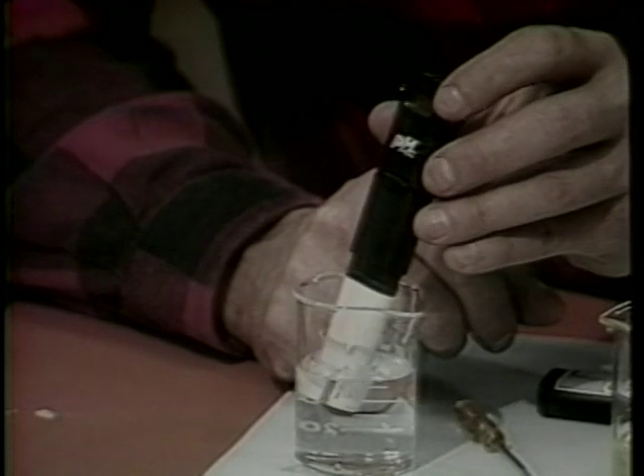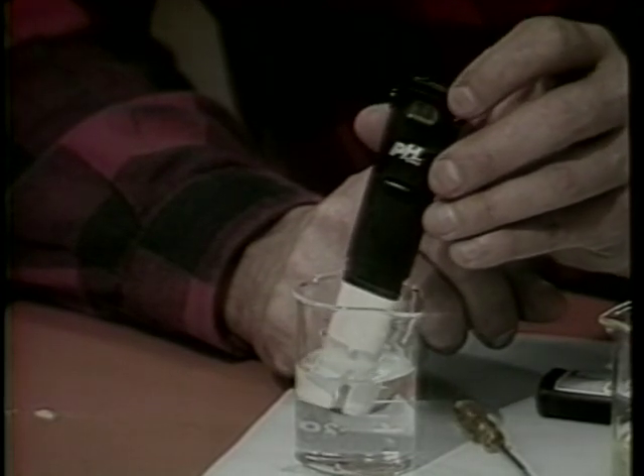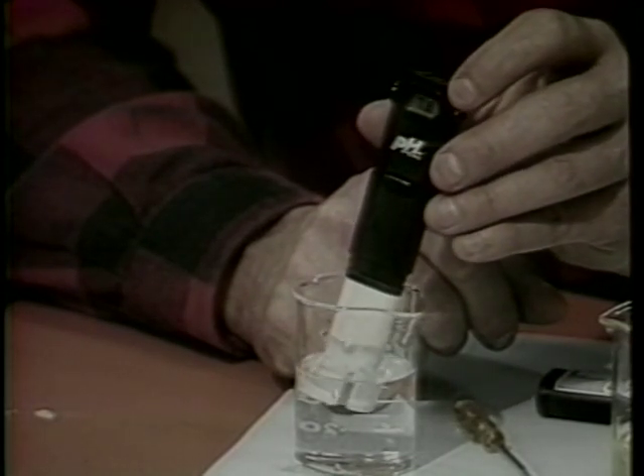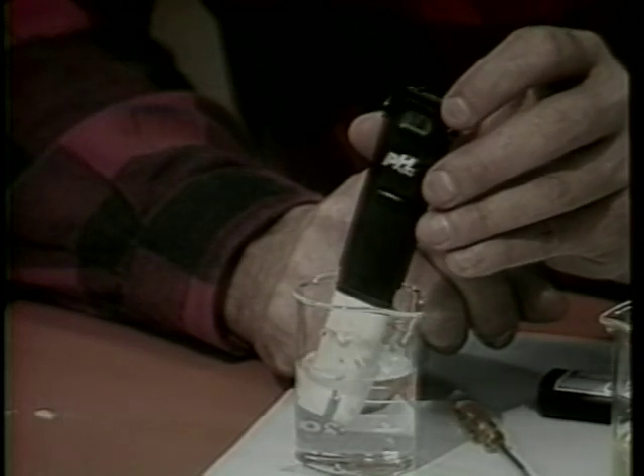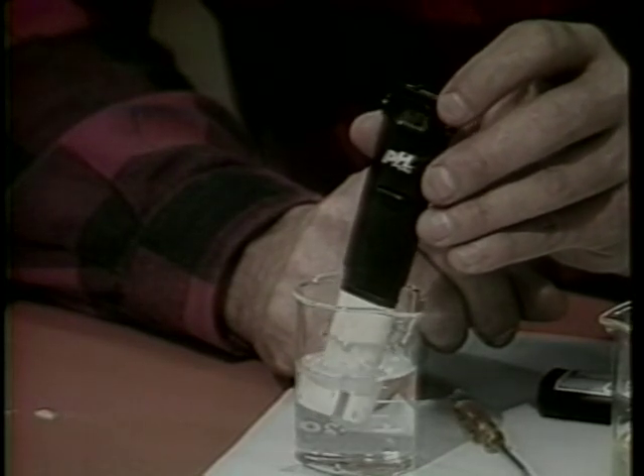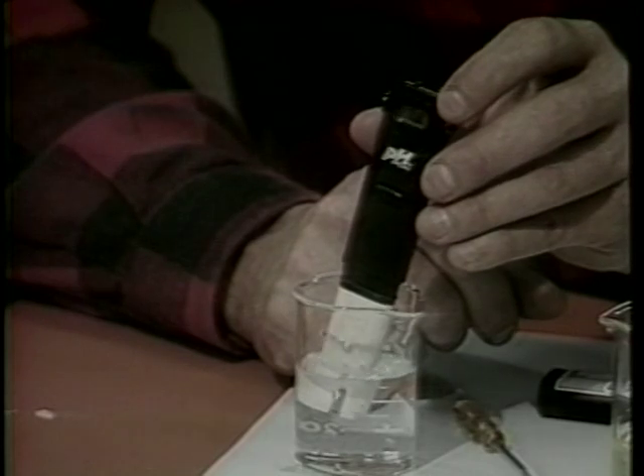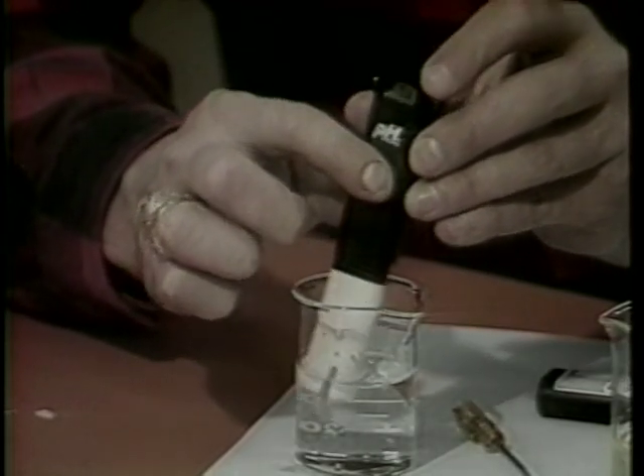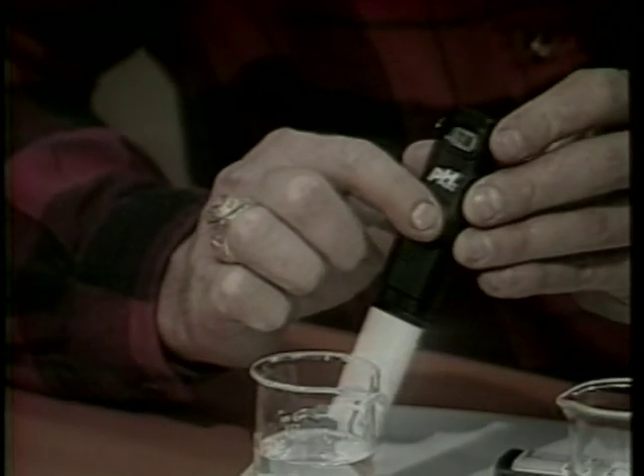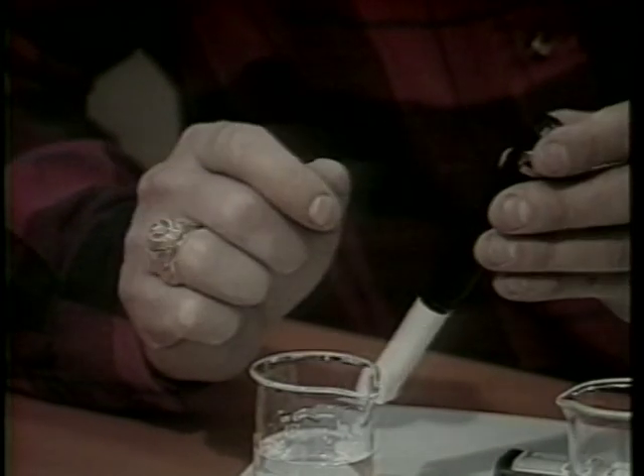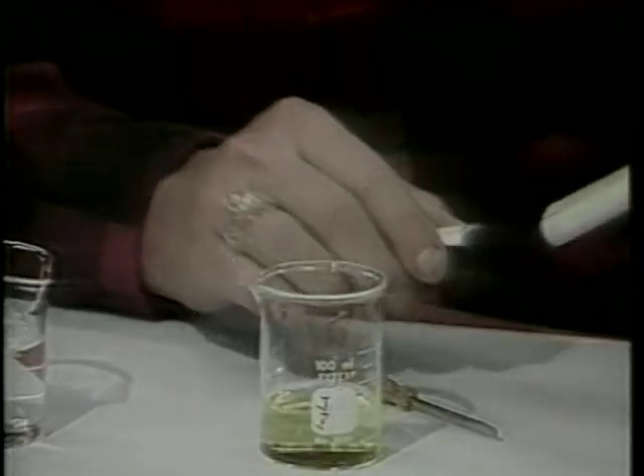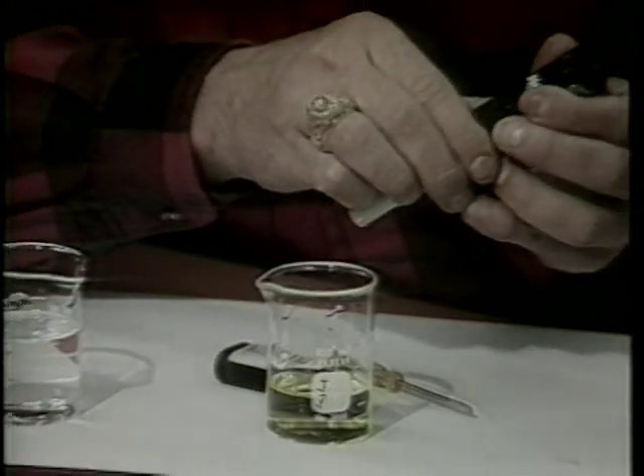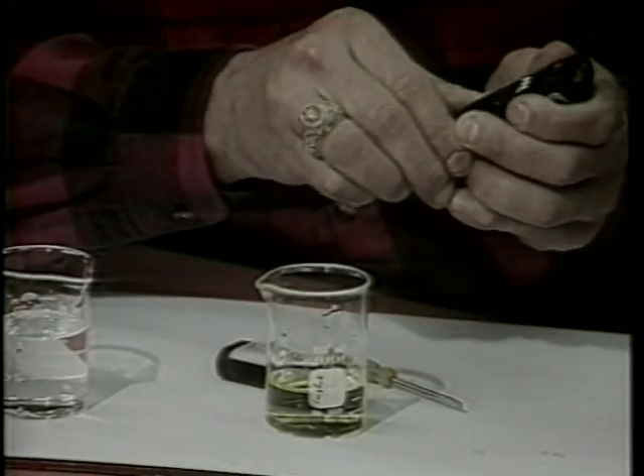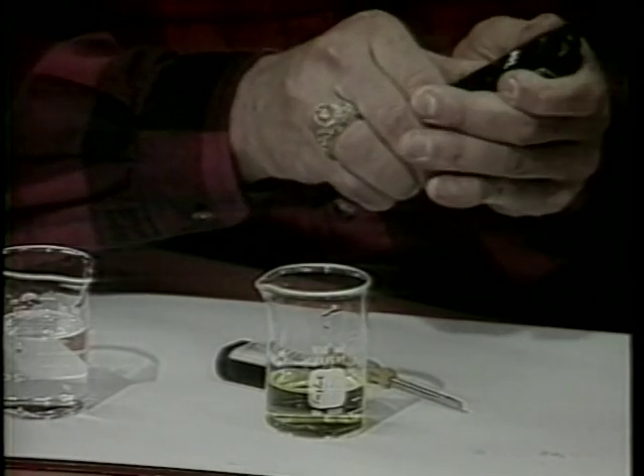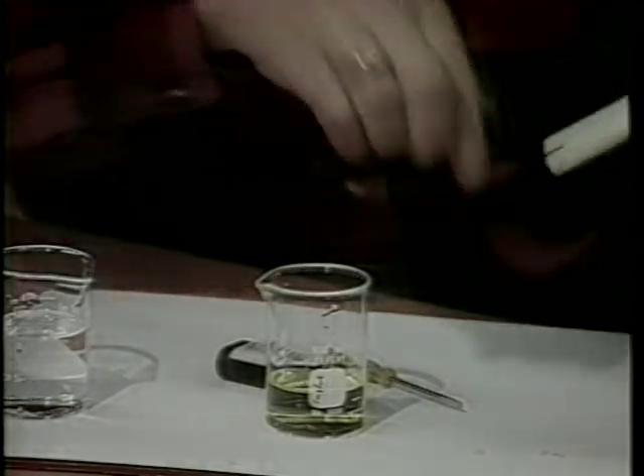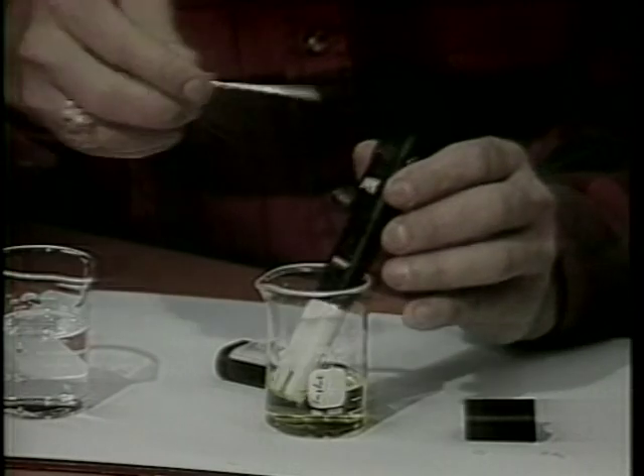The pH may also be measured with a meter, but most meters are expensive. However, a less expensive version of a typical pH meter is available. An example of this is commonly called a pH pen. To use this instrument, proceed as follows. Remove the plastic boot from the meter. Check the calibration of the meter by immersing the probe into a buffer of a known pH. The buffer should be within the normal pH range of the pond.